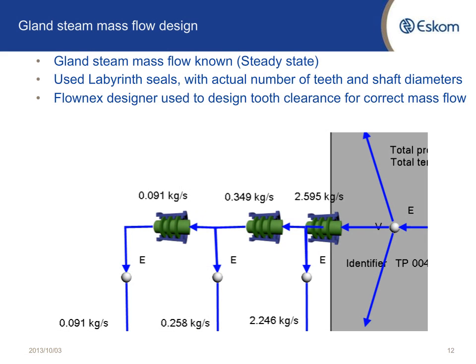For the gland steam mass flow design, once again the gland steam mass flow is known for the steady state. I used labyrinth seals with the actual number of teeth and shaft diameters to model the labyrinth seals, and then I used the Flownex designer to design the tooth clearance to get the correct mass flow.